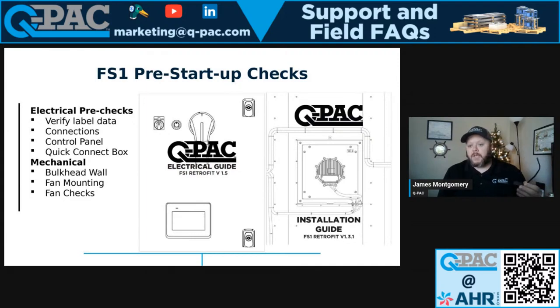So it sounds like a given, but it happens where someone orders a 208 volt system and they apply 460 to it or vice versa. That's actually pretty detrimental to certain components. So the majority of our fans are dual voltage. When you're buying a 208 system, those fans are usually dual voltage, but still we've got some components that are specific to that voltage. And so you'll need to verify that.